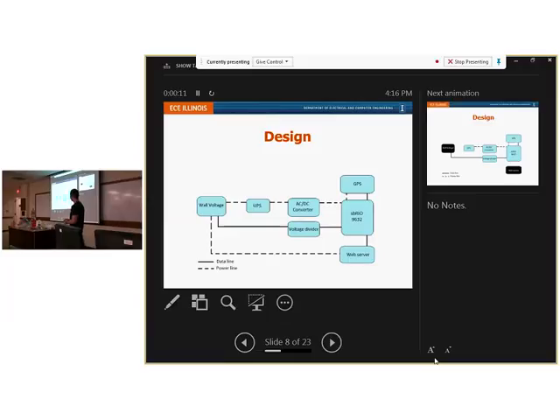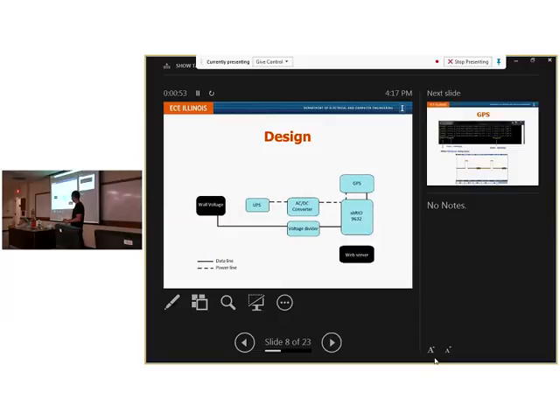So during normal operation, there's a voltage coming from the grid that powers our UPS, and in turn we get power to the sbRIO, and also we use a voltage divider to step down the wall voltage so that we can read it using the sbRIO, because the sbRIO has a maximum voltage input of 10 volts. So we have to step down the grid voltage to a maximum amplitude of 10 volts. And then we also get a GPS timestamp in our data, and then we upload that data to a web server. Now, when there's a blackout, there's no more voltage at the wall outlet, and the web server is out. But that's okay because we have the UPS to back up our PMU, so we are still able to process what's happening at the grid through the voltage divider and store all that data internally until the power becomes available. Then we upload the data to the web server.